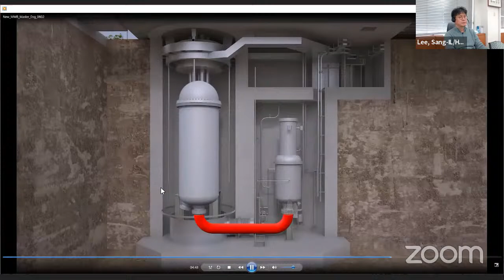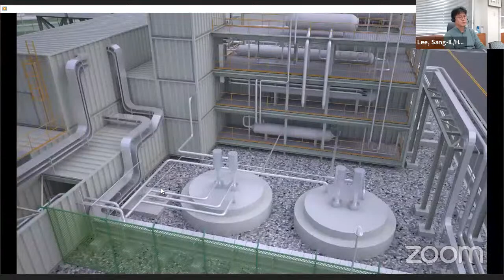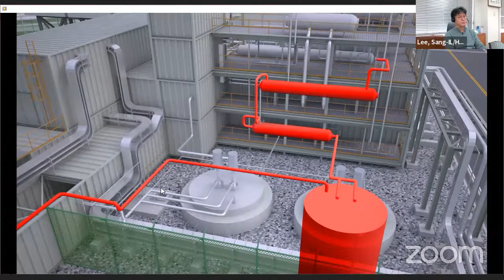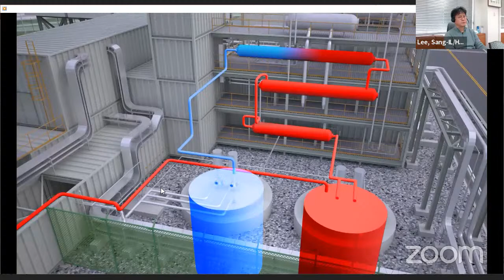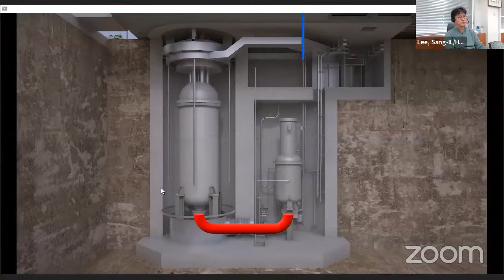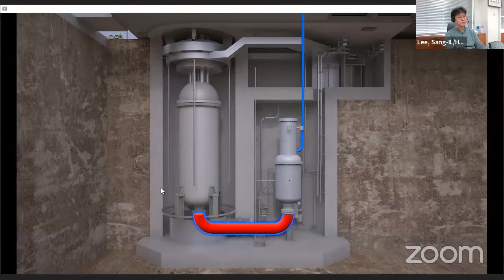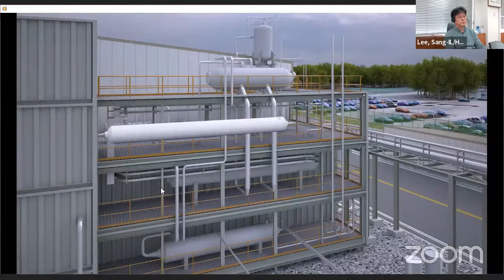The helium heated by nuclear fission energy in the reactor goes to the intermediate heat exchanger. The molten salt heated by hot helium in the intermediate heat exchanger transfers to the hot molten salt tank. The hot molten salt exchanges heat with feed water through the superheater, evaporator, and economizer. After heat exchange, the cold molten salt is sent back to the intermediate heat exchanger for recirculation through the cold molten salt tank. The cold helium is recirculated to the reactor by the circulator after heat exchange with molten salt in the intermediate heat exchanger.